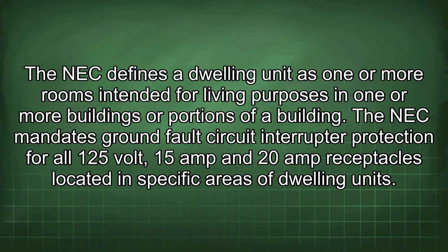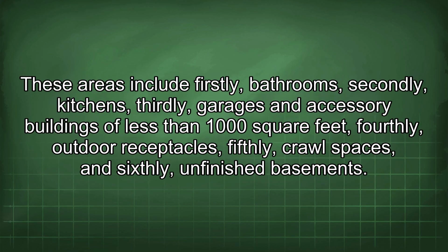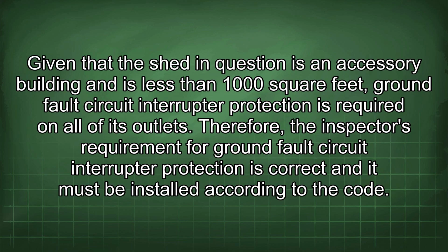The NEC mandates ground fault circuit interrupter protection for all 125-volt, 15-amp and 20-amp receptacles located in specific areas of dwelling units. These areas include, firstly, bathrooms; secondly, kitchens; thirdly, garages and accessory buildings of less than 1,000 square feet; fourthly, outdoor receptacles; fifthly, crawl spaces; and sixthly, unfinished basements. Given that the shed in question is an accessory building and is less than 1,000 square feet, ground fault circuit interrupter protection is required on all of its outlets.